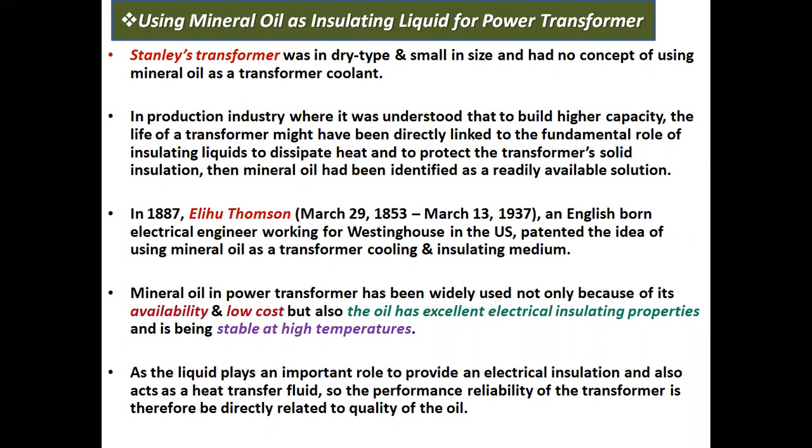Now let us discuss mineral oil. Using mineral oil as insulating liquid for power transformer. Why is it used? Initially, the transformer was dry type and small in size and had no concept of using mineral oil as a transformer coolant. In the industry, when it was understood that to build higher capacity, the life of a transformer might be directly linked to the fundamental role of insulating liquids to dissipate heat and to protect the transformer's solid insulation, then mineral oil was identified as a readily available solution.